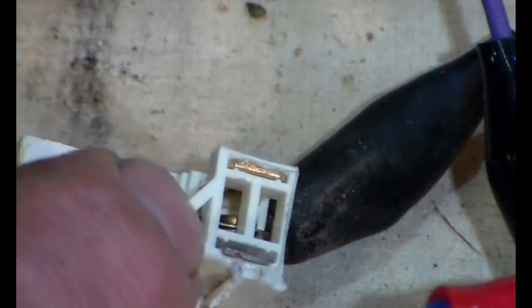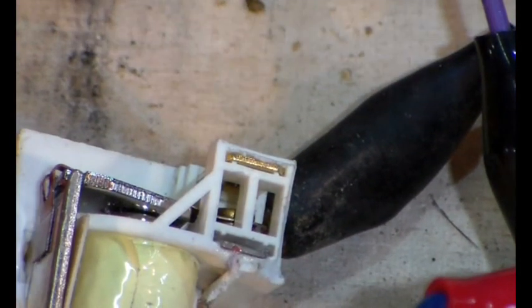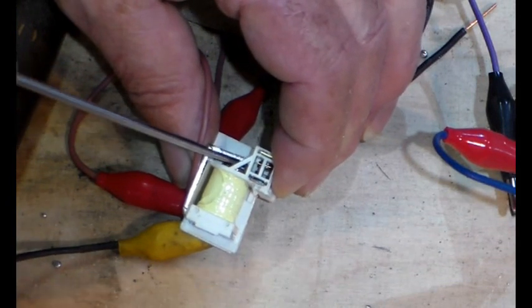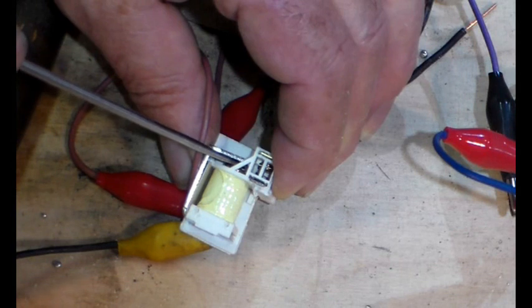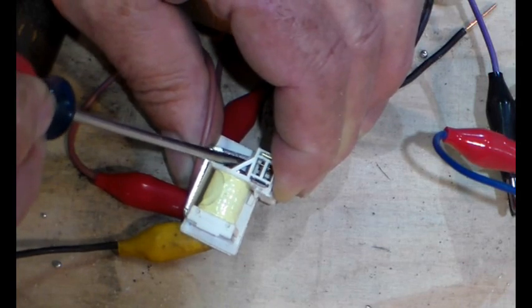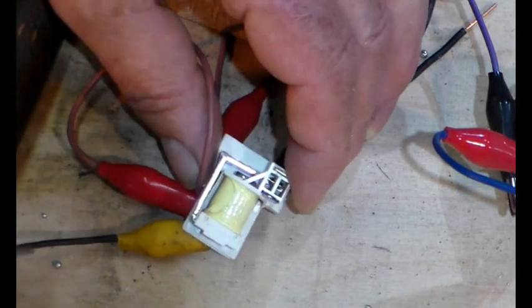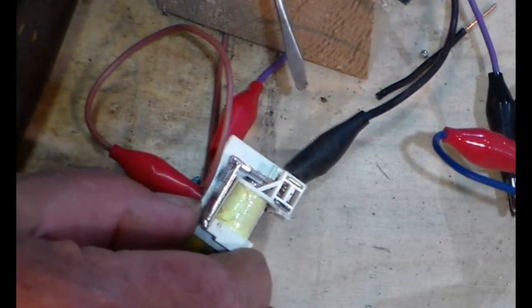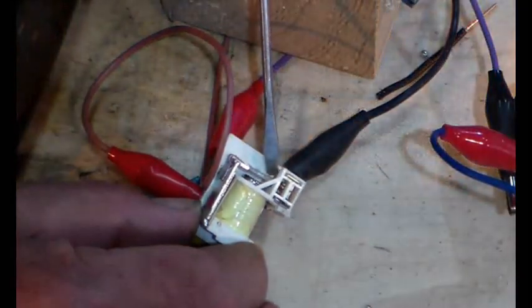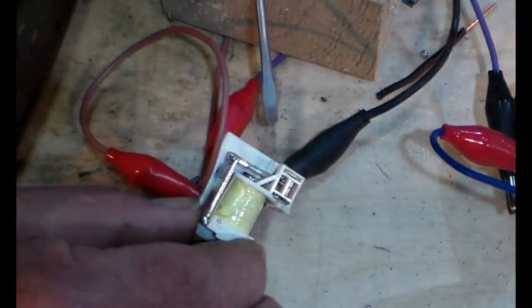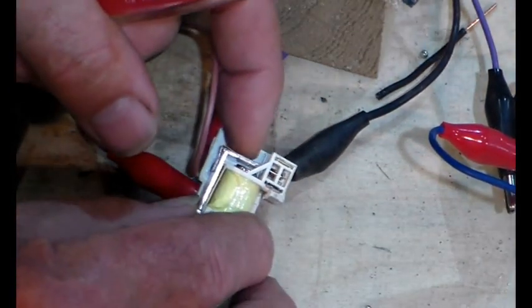So what we need to do is we need to adjust these contacts. Hopefully that makes sense. So it's switched off. So what I propose to do is put a screwdriver between the moving arm and the solenoid core and just twist the screwdriver. So now, manually operating this, it works, it works, but I don't think it's quite enough because there needs to be...